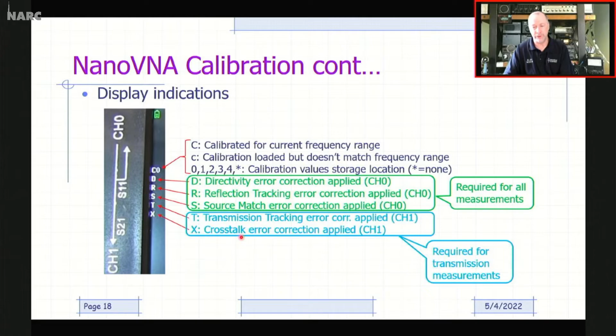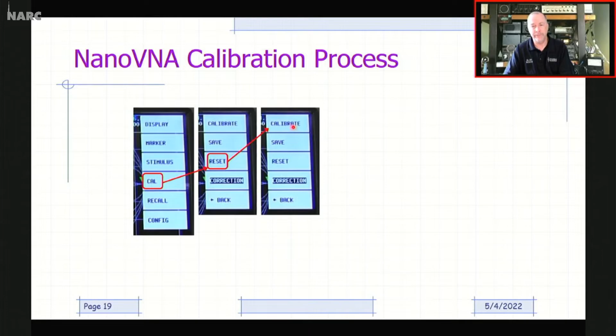So let's look at the process, okay? And this kind of walks you through a little bit of the way the user interface works. So we start with the main menu, and we select Cal. You'll click on Cal, and then you get the calibration menu. Next thing we want to do is hit the reset button. The reset will clear out the current calibration and get you ready to run a new cal. So once you hit reset, you're still on the same menu. You can touch on calibrate.